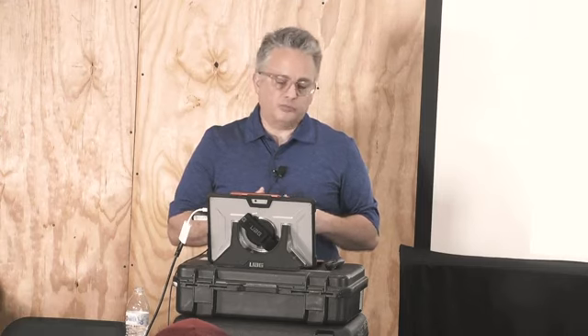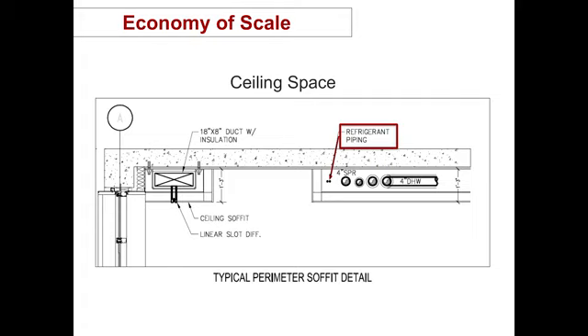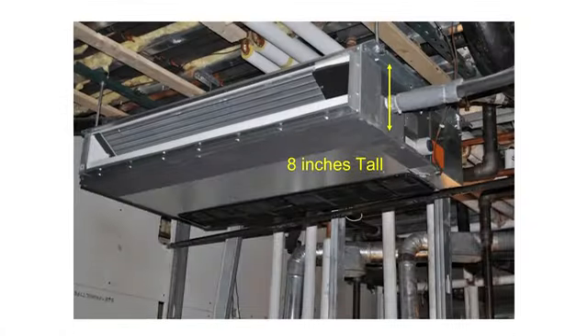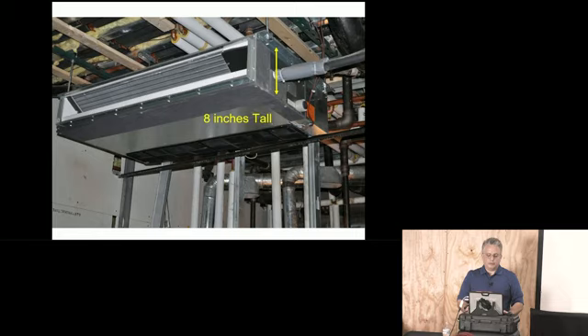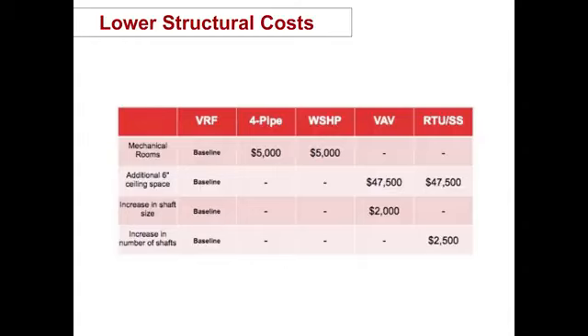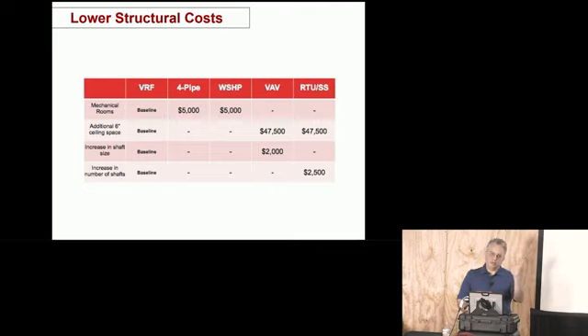But with VRF, or ductless technology in general, here you can see illustrated what is required. And there is an argument that if you have a 10-story tall building, you may be able to not pay for one full story of it just because of the ductwork that you're not installing. Here we have an example indoor unit that is about 8 inches tall. This is a ducted unit, medium static, which is about 0.6 ESP. So lower structural costs. This slide is, admittedly, for architects more than contractors, but just gives you a dollar amount of what can be saved with VRF as your baseline.